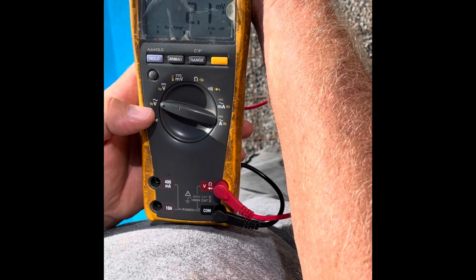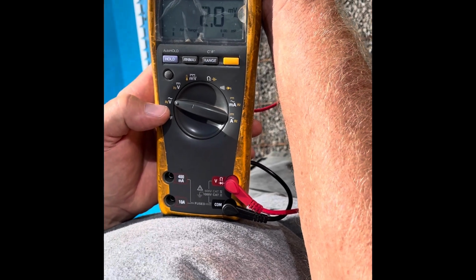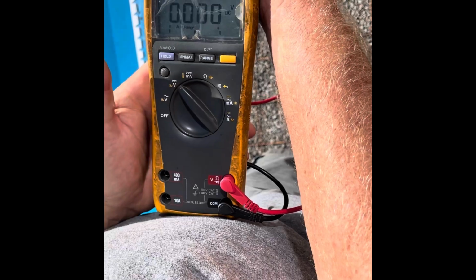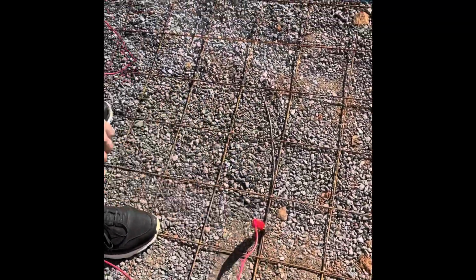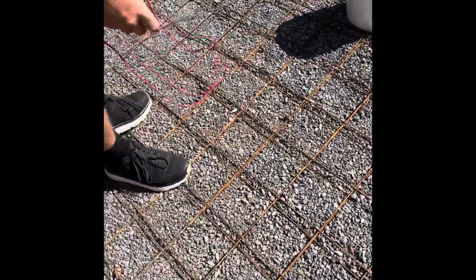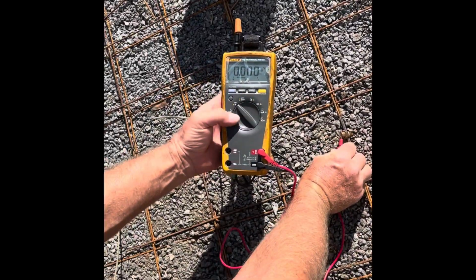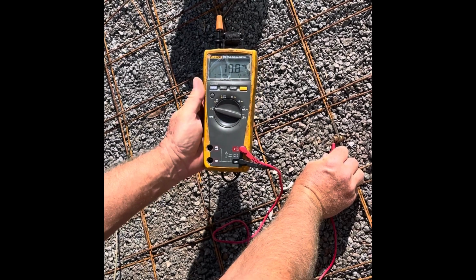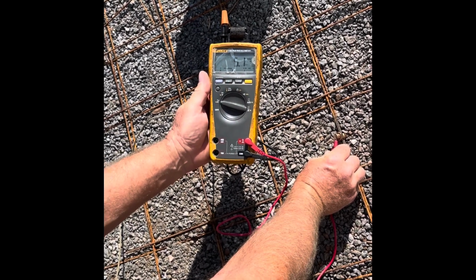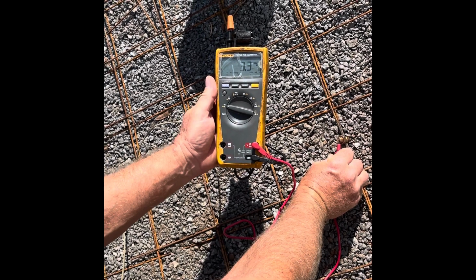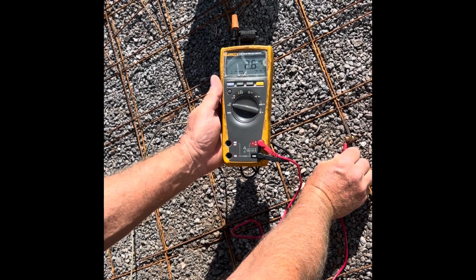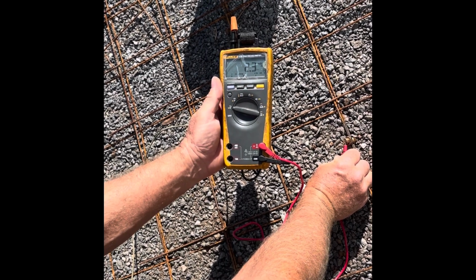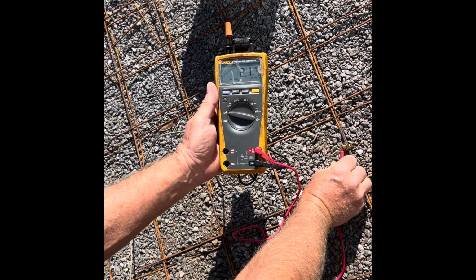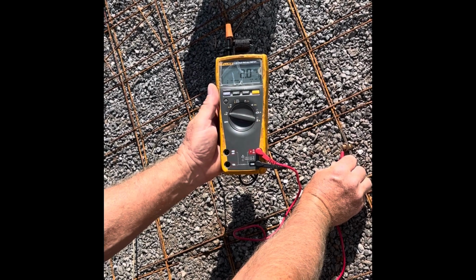That's about where you're going to get to. That's about how long it takes to settle on the AC mode. When we go to DC, you'll see it goes straight to 0. So when we connect back to the grid, to a split bolt, and then we go to any other point on the grid, like we did with our continuity test, we're going to see our DC voltage is at dead zero. Our AC voltage is now at about a 2.3, very little difference, as you can see.